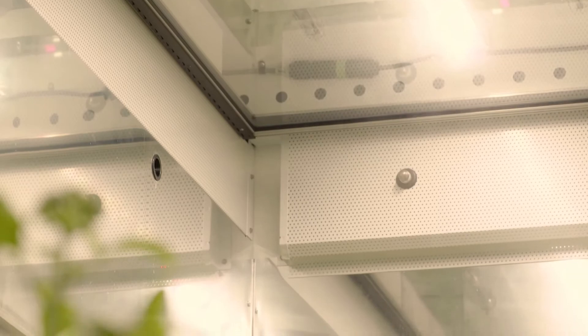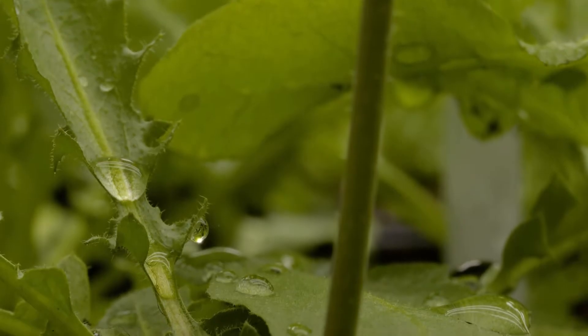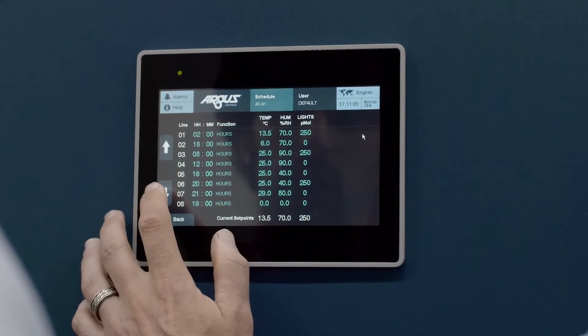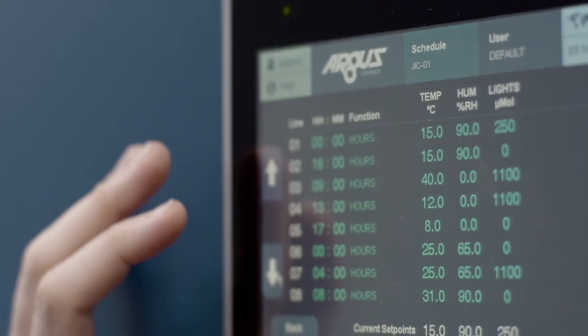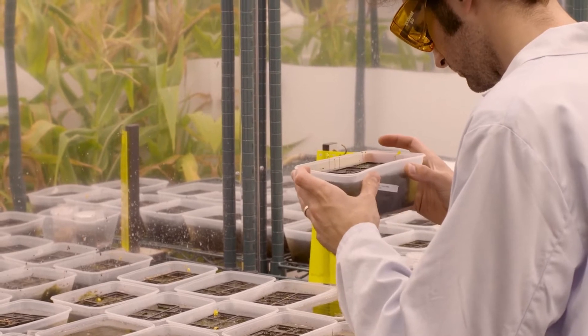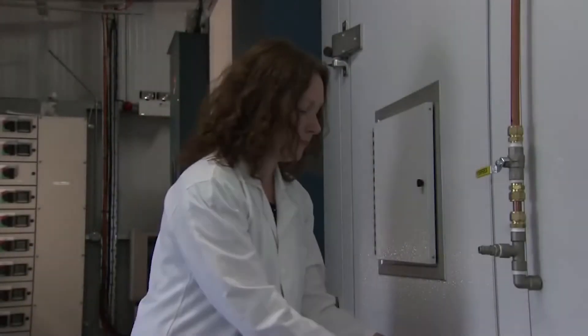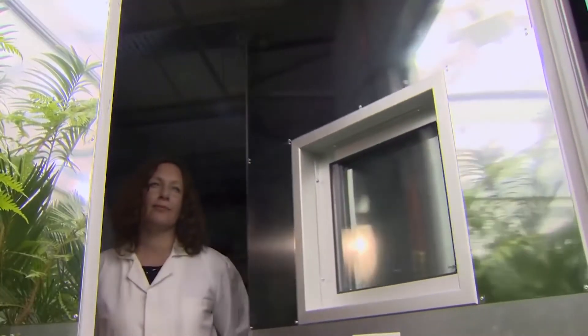Plant growth chambers and rooms are often sold without active humidity or dehumidification. However, while controlling humidity is not considered standard, it can be important to ensure consistent plant response and subsequent interpretation of experimental results. You may think that you're controlling all the critical aspects of your controlled environment experiment, but without active humidity control, you're subject to the vagaries of the conditions surrounding the chamber, due to the fact that there's air exchange from the outside of the chamber to ventilate it.